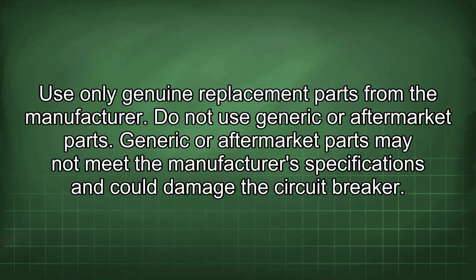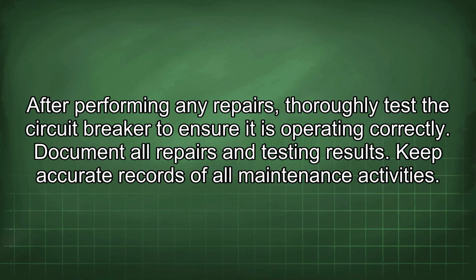Use only genuine replacement parts from the manufacturer. Do not use generic or aftermarket parts. Generic or aftermarket parts may not meet the manufacturer's specifications and could damage the circuit breaker. After performing any repairs, thoroughly test the circuit breaker to ensure it is operating correctly. Document all repairs and testing results. Keep accurate records of all maintenance activities.